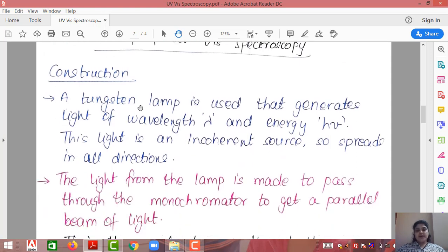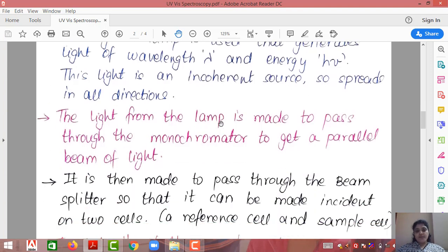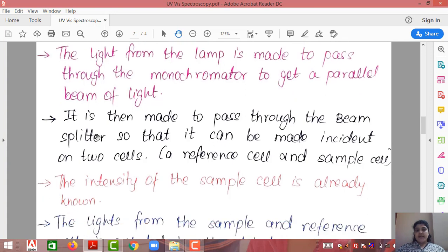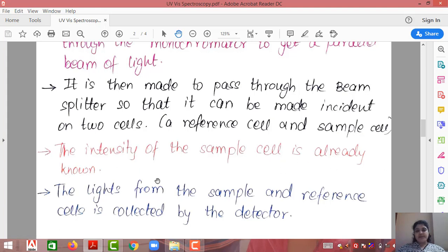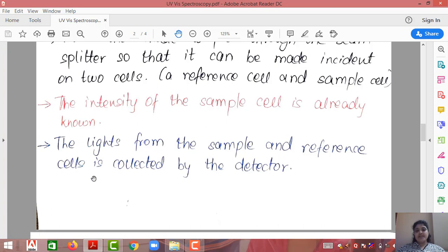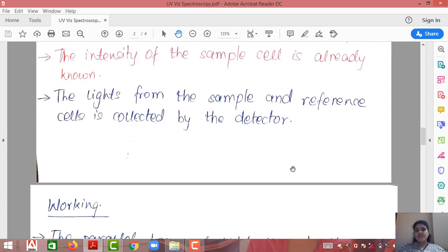Construction pointwise: A tungsten lamp generates light of wavelength λ and energy hν. This light is an incoherent source and spreads in all directions. The light is passed through a monochromator to get a parallel beam. It is then passed through a beam splitter so it can be incident on two cells, since we need to compare two intensities. The two cells are a reference cell and a sample cell. The intensity of the reference cell is calibrated at I₀. The different intensities from the sample and reference cells are collected by the detector.